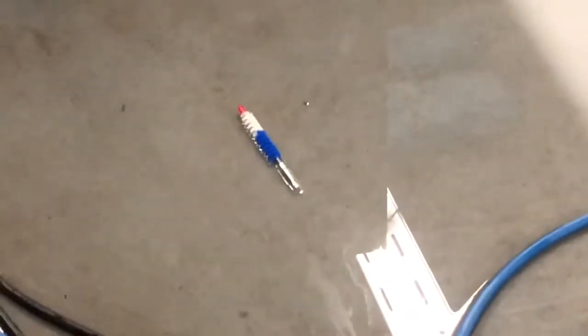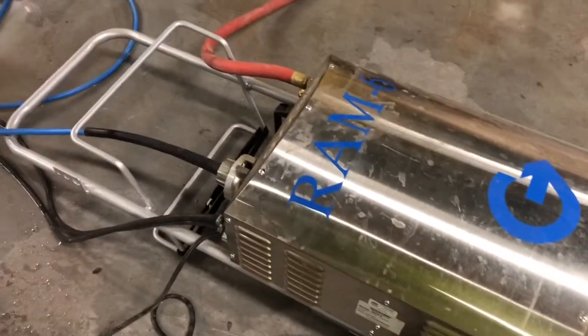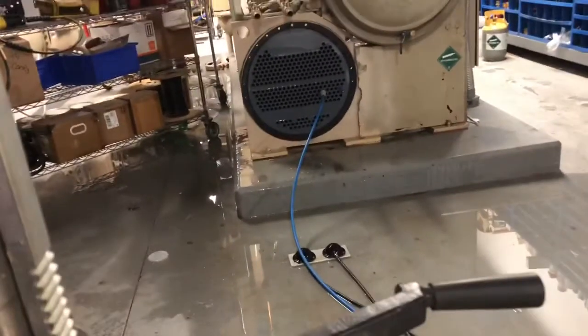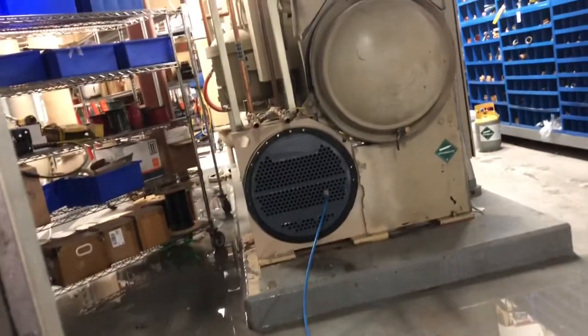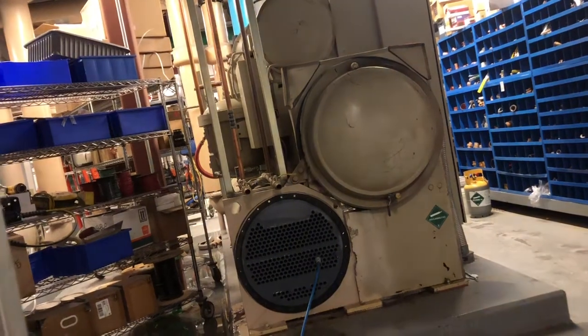There on the ground is the brush that's attached to the end of the cable that's running in that blue tube, and there is the machine that drives the cable. It's got water hooked in on the top of it, and the blue cable on the bottom. The brush is sticking out the back of the chiller right now, and when you push on the foot pedal, it begins to rotate, spins forward and reverse.